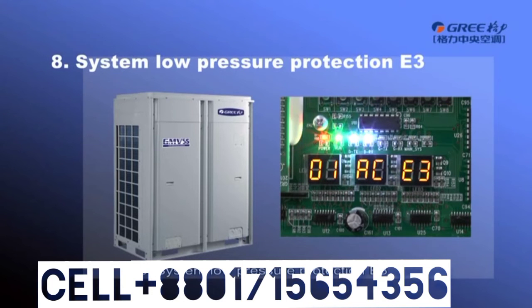8. System low pressure protection E3. Possible causes. First, the cutoff valves of the outdoor units are not fully opened as required. The checking method is the same as E1. 2. Fan is not working properly. The checking method is the same as E1. 3. Low ambient temperature in operation. The lowest outdoor temperature in cooling is -5 Celsius degrees. The lowest indoor and outdoor temperature in heating is 10 degrees and -20 degrees respectively. When the actual ambient temperature exceeds the limit, E3 may appear, which is a normal phenomenon.